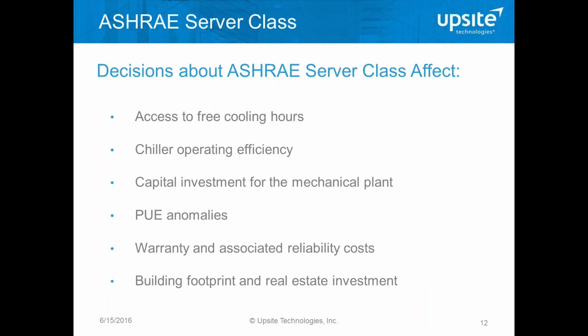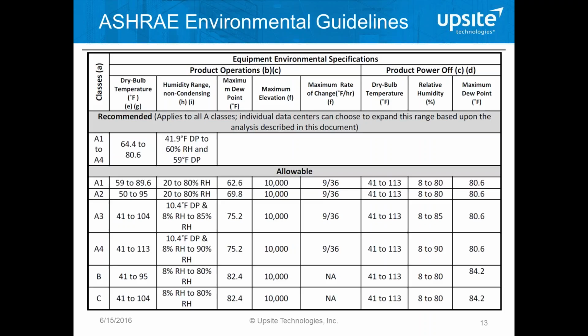Warranty costs also bear into this, and real estate costs as well, because if we can avoid the mechanical plant and all the associated hardware and real estate required for that, that would realize those savings as well. So the specific classes we're looking at are on this ASHRAE chart in the far left-hand column. You see them in the middle of the page there, the A1, A2, A3, and A4. Like I said, you probably won't find these advertised by the server manufacturers, but what you will find is in their user documentation these operating temperature ranges. And so those are the temperature ranges that will produce those results that we talked about on the previous slide.